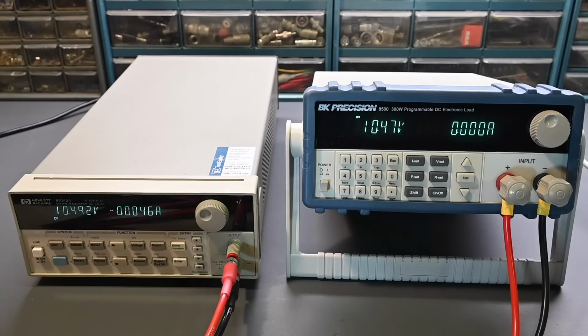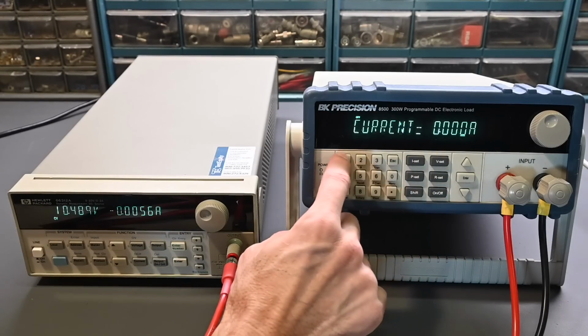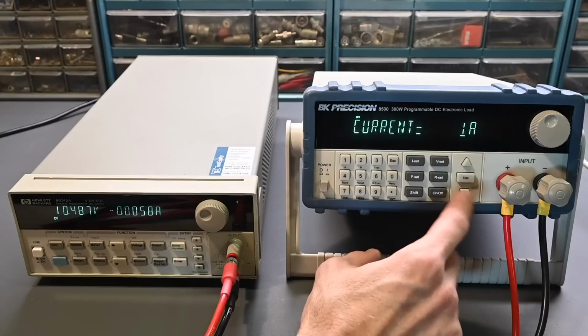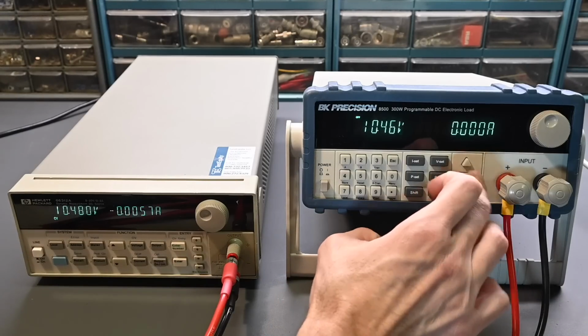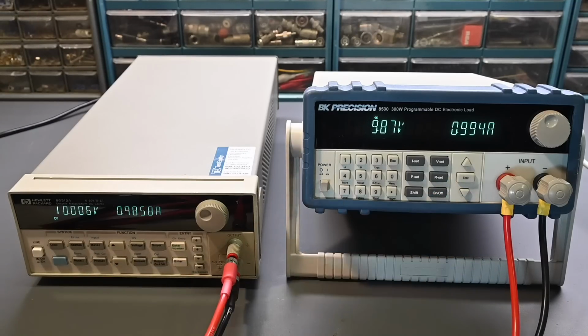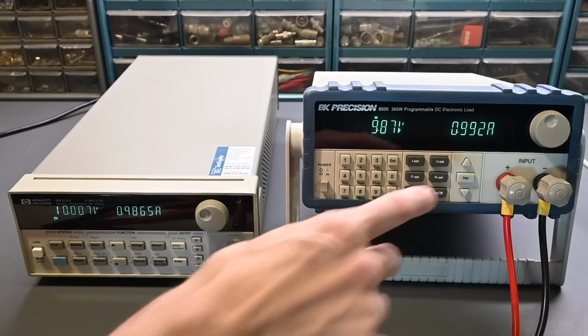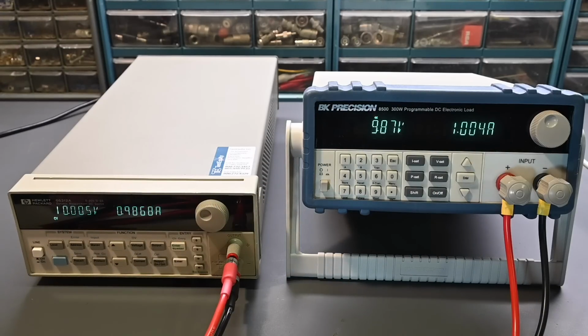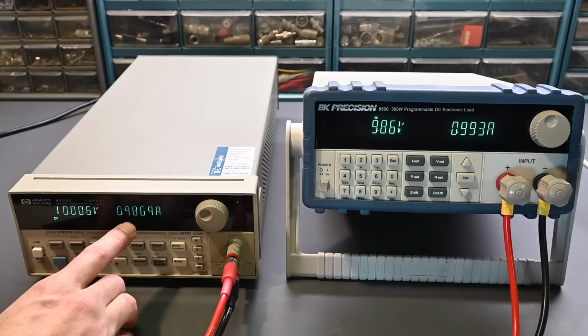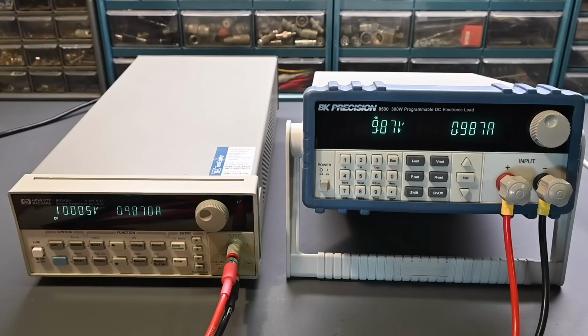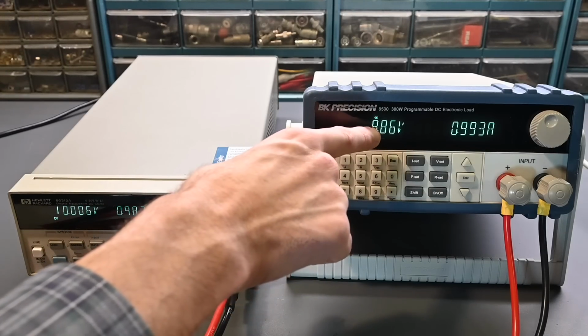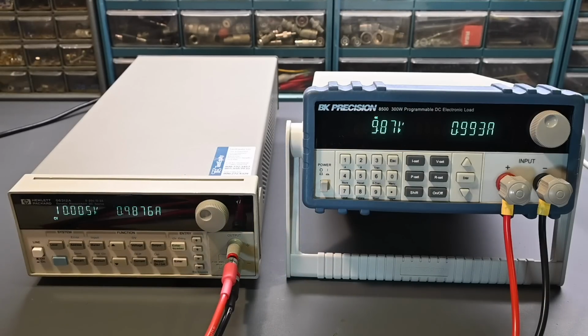So let's give it some load. Let's say 1 amp. So we'll go over here, current set, go 1 amp. Here, enter, and turn that on. Okay, so it's sitting right at 1 amp, no problems there. This is indicating also about 1 amp. Numbers are almost in agreement there. Again, probably needs to be calibrated, but nonetheless very, very close. The voltage has actually come down. It's settled in closer to that 10 volt value, which is interesting. And a little bit of loss in the cable, so it's normal that this would be down just a little bit. So really no issues there. It looks pretty close.